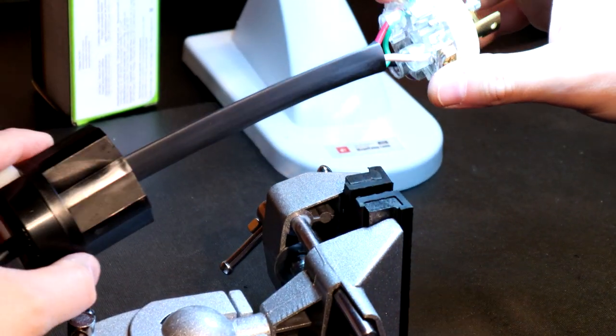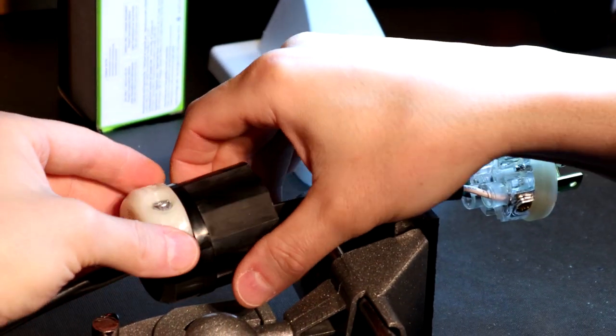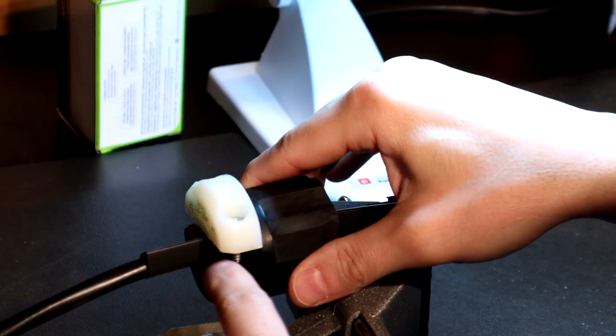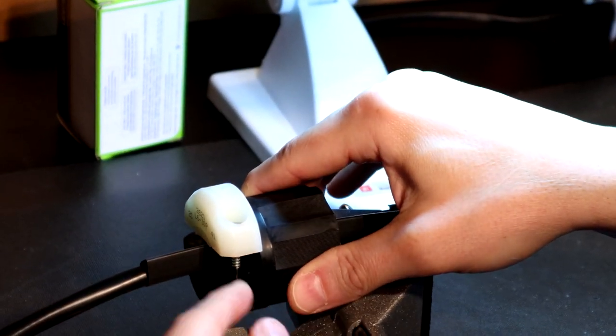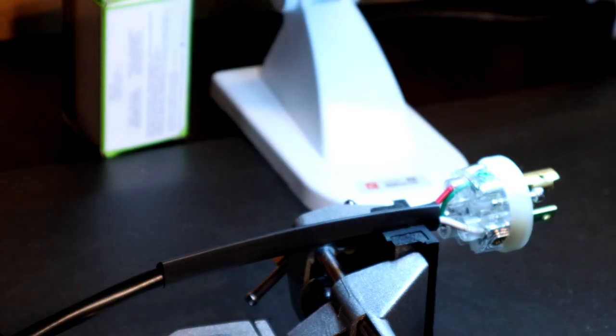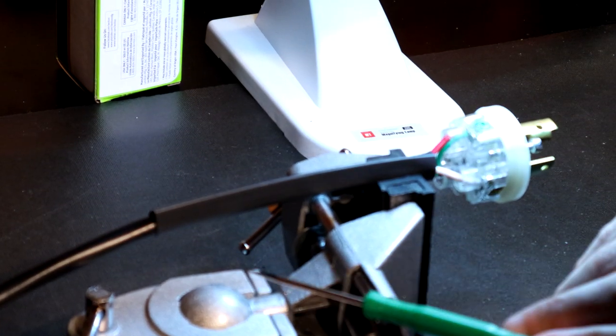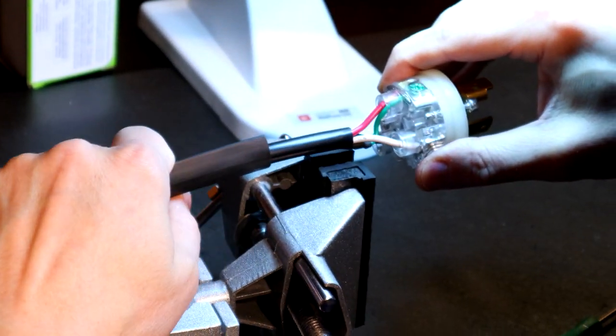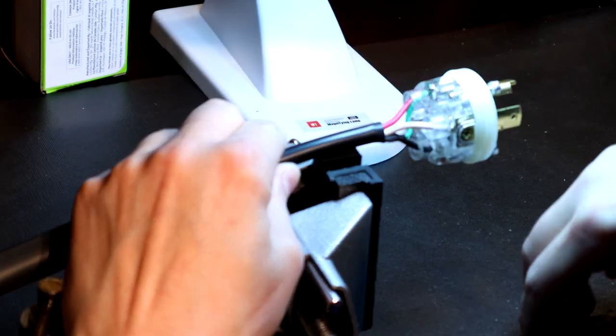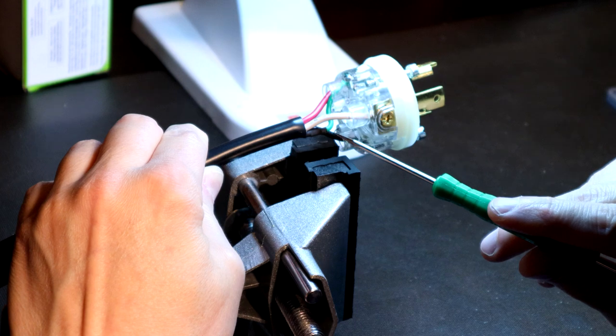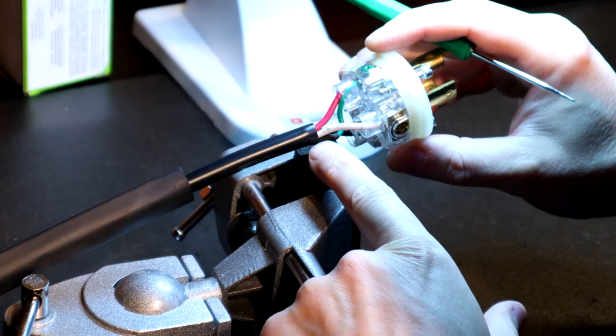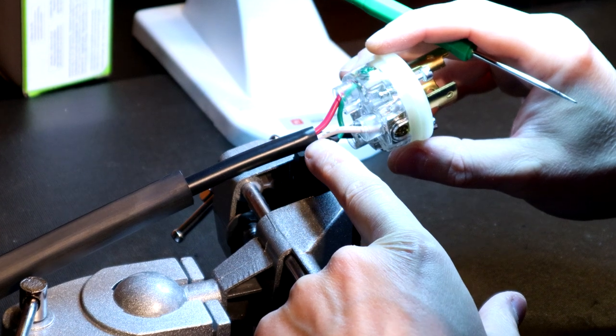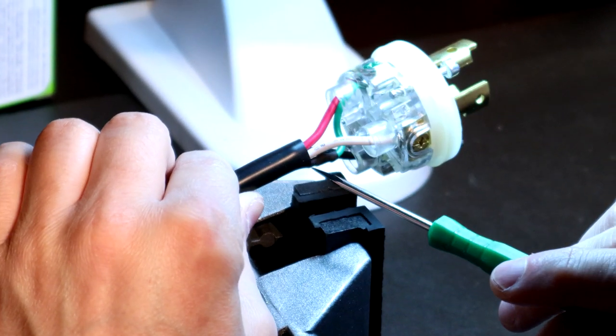The main reason we do that is so that this stays nice and wide up here where it fans out to our leads. It's not going to put excess stress there. By the time it actually joins to the cable, you're actually formulating and encasing this cable with that double wall heat shrink, which will become plastic. When we bring the butt cap end up, we make sure that our stress relief has been created this way. So it'll make contact with the double wall heat shrink, and this way you know you're not going to chafe any of your cable's PVC casing. A lot of guys always say to me, it's like you're doing surgery. And it is. It's very much the same as what you'd see with surgery to do this right.